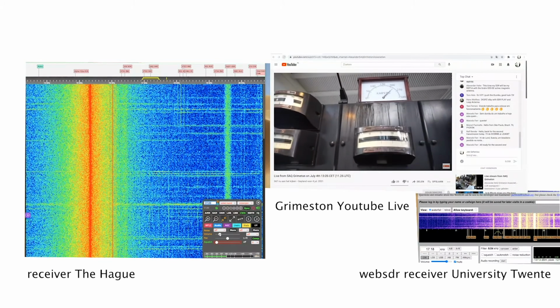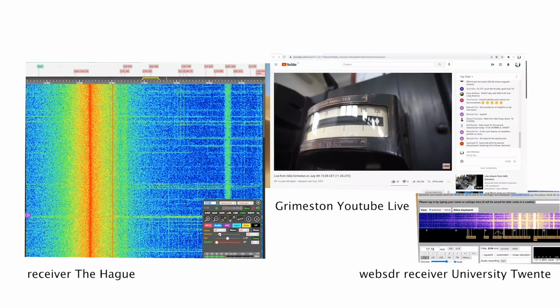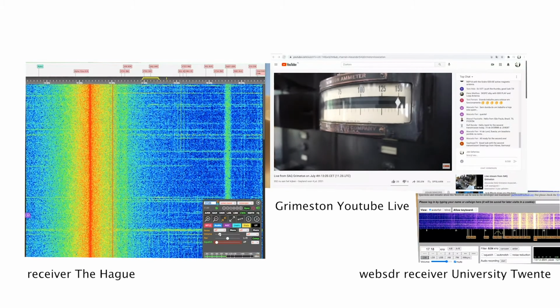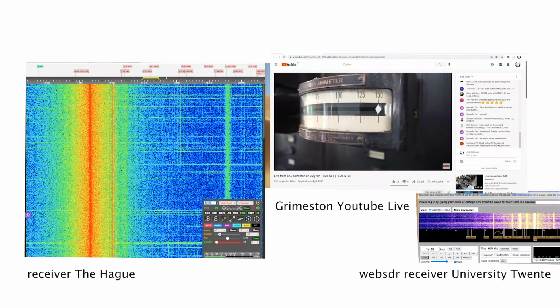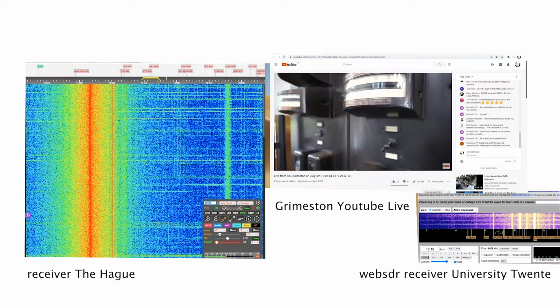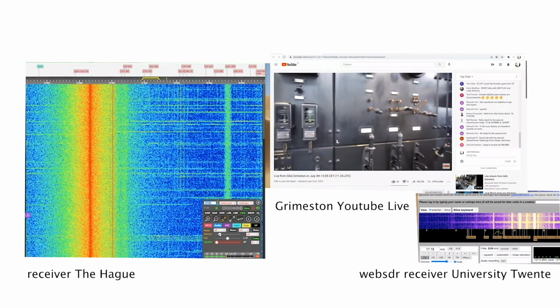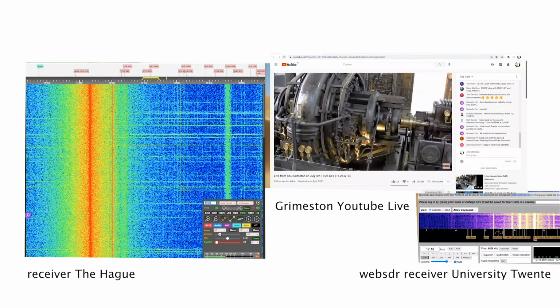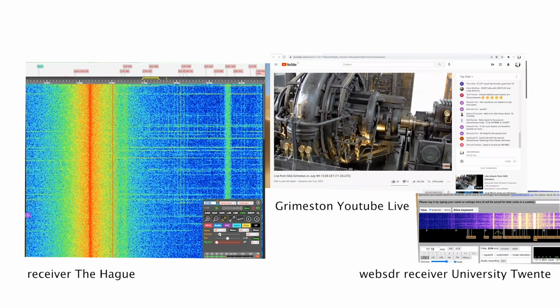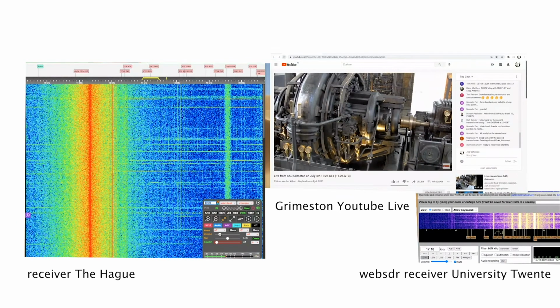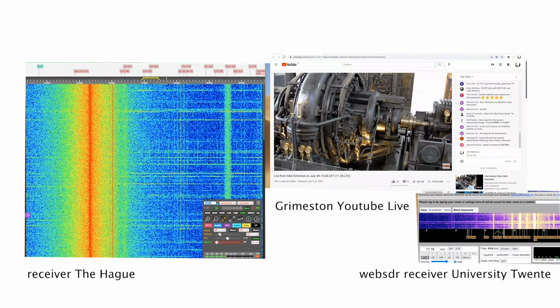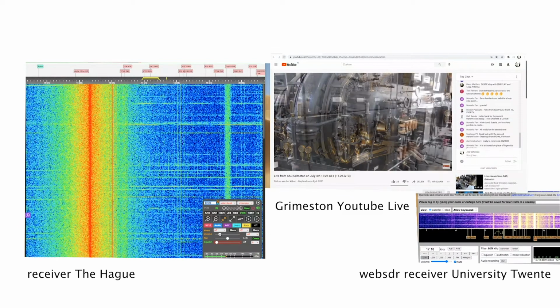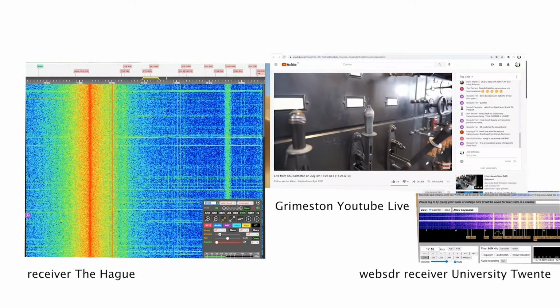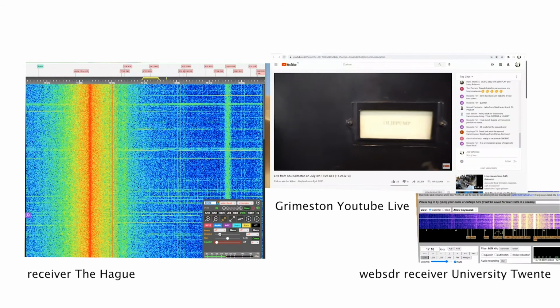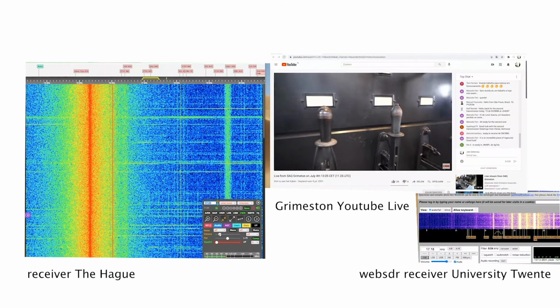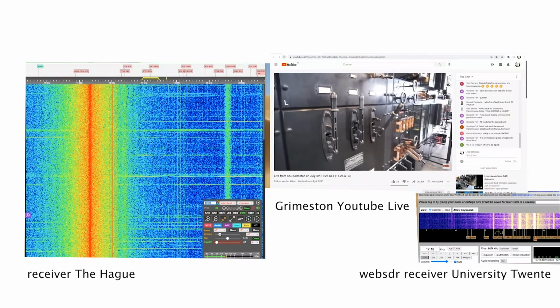We are now waiting for the internal oil pump in the transmission unit to handle the lubrication, and we can stop the auxiliary oil pump. We are also waiting for the motor to rev up and that the motor current will go down to 100 amps. Then we will go on and start two rectifiers, rotating converters, one which gives 125 and 250 volt DC, and the other gives 500 volt DC. This voltage is needed to control the transmitter.